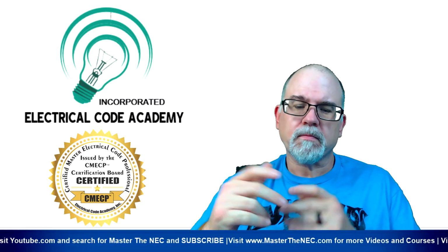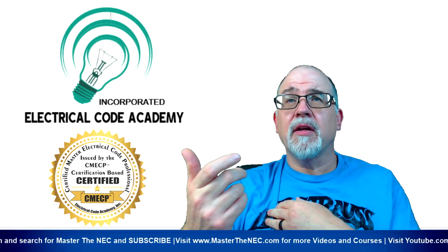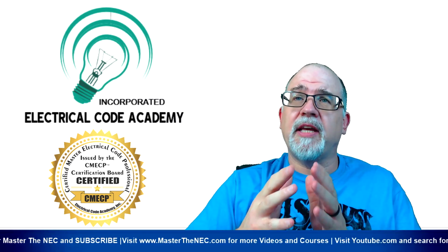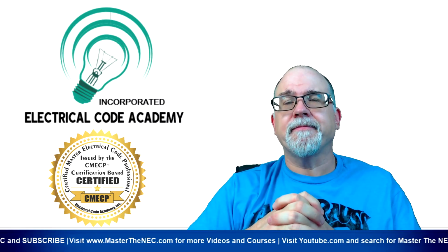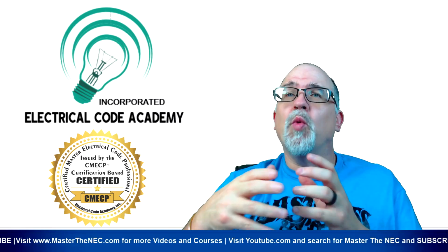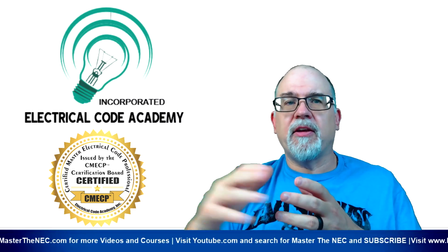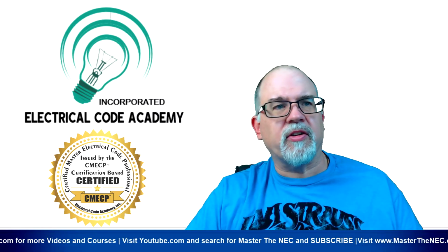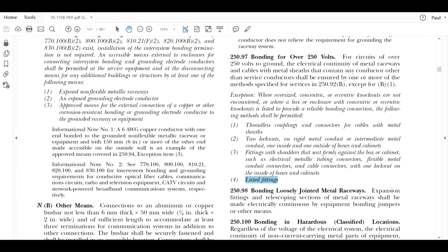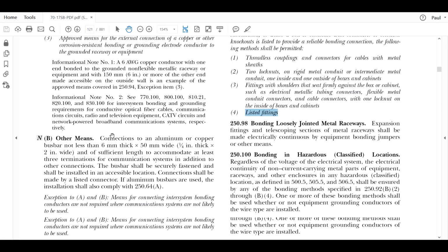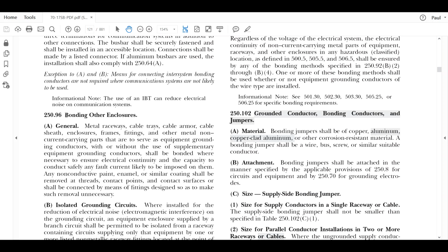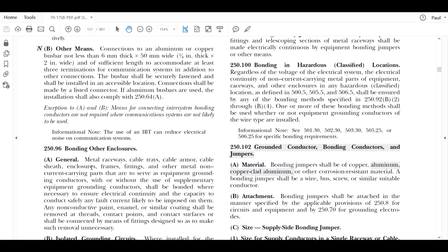All right, so if that FMC gets energized, then it is bonded using a listed fitting to the enclosure, and all the bonding has been done, and you're okay. There is a requirement in 250.96, and we'll go look at it real quick. This is just a general rule, so it's good to make sure that you follow it. 250.96, just so we can read it, is dealing with bonding other enclosures. So it just says that equipment, blah, blah, blah, framing members, and all of that are to serve as equipment grounding conductors. All right. And of course, that FMC is not serving as an equipment grounding conductor. Okay. So keep that in mind. All right. So you don't get confused with that.